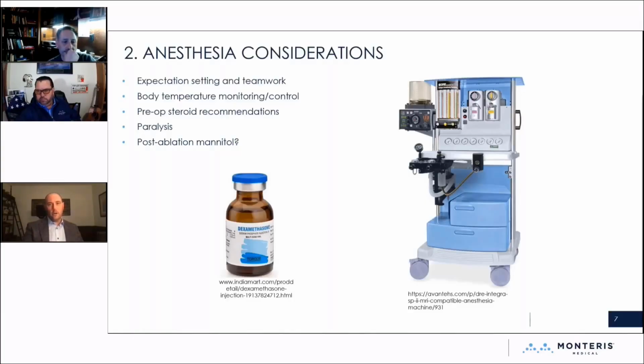I think the big things here are we actually like the Bair Hugger in these cases because it's going to warm the patient to a point where it starts them at a higher temperature, and that actually allows you to get to your cooking temperatures faster. So it'll speed up your case if your baseline temperatures are actually a little bit higher. So is it crucial? No, but it's helpful. You want your anesthesia folks to have a temperature probe because it's a good backup to the temperature probe on the laser, and that's going to allow you to set your reference temperatures that you can use to essentially calculate.